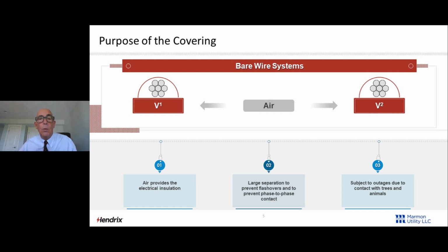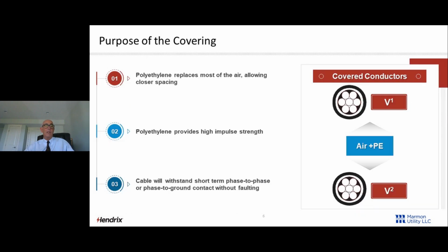Even though the bare wire system is the cheapest and the easiest, it's still subject to outages due to contact with trees, contact with animals, birds, if you will. So what we do is we put a little bit of polyethylene insulation on those bare conductors. Now that polyethylene is a really darn good insulator. It replaces that air. So now we're able to bring those phase conductors much closer together, and actually we can have them 1 inch from each other. That's how good the insulation is.